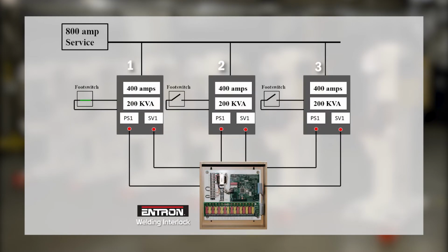Machine 1 is initiated and valve output SV1 turns on. When SV1 turns on, the interlock checks to see if any other machines are looking to fire. There aren't any other machines in sequence, so permission to fire is given by closing the pressure switch input on machine 1. Machine 3 is initiated and requests permission to fire.